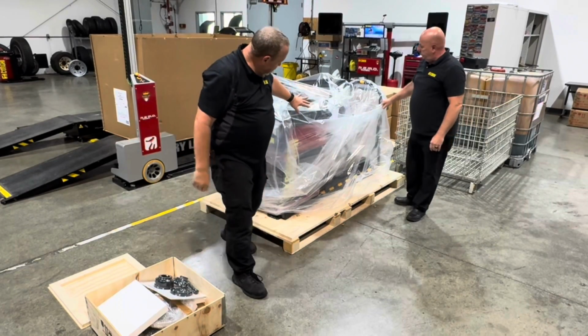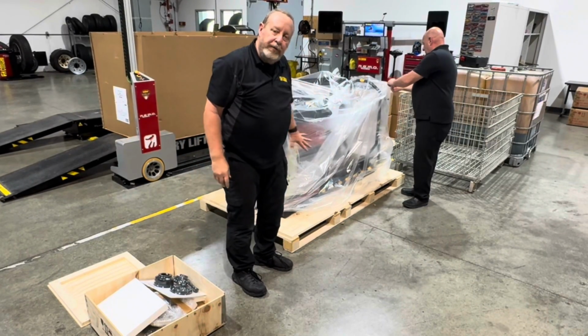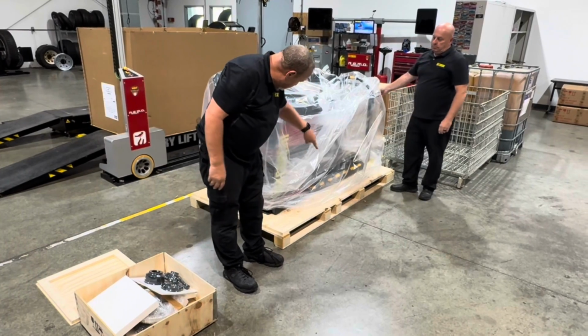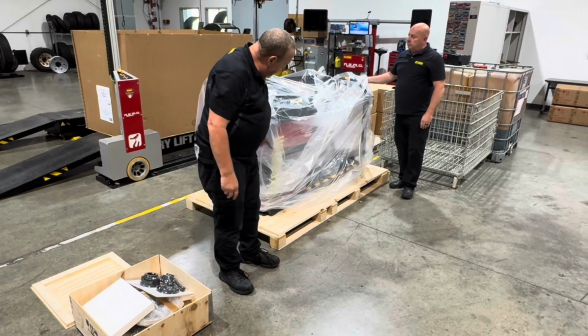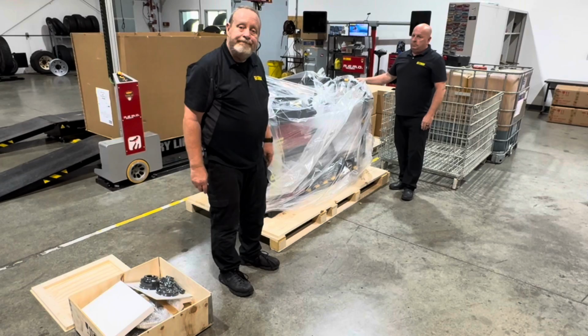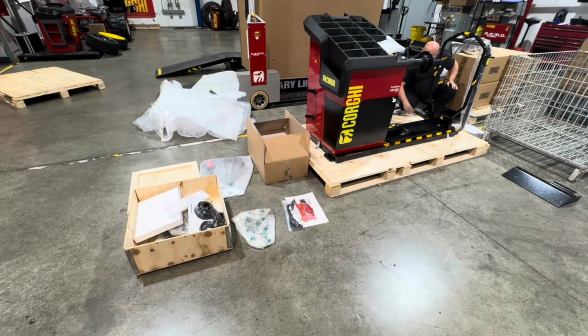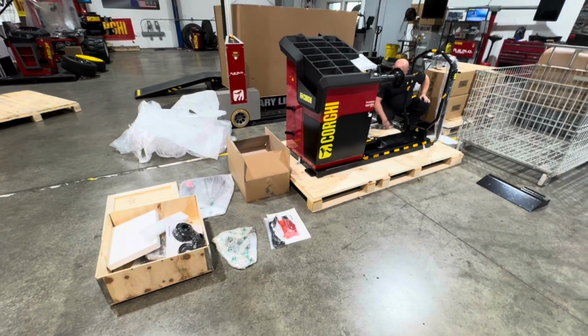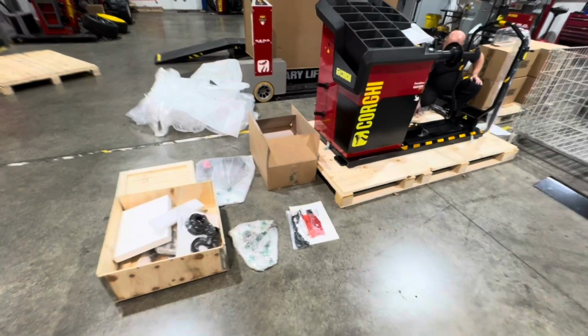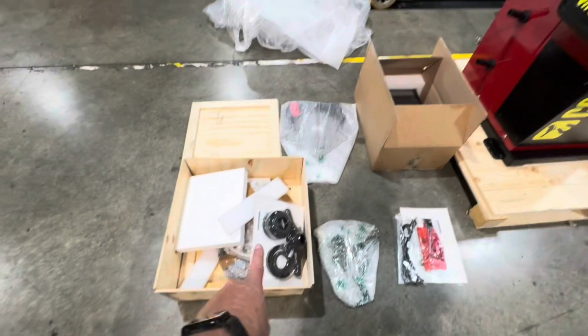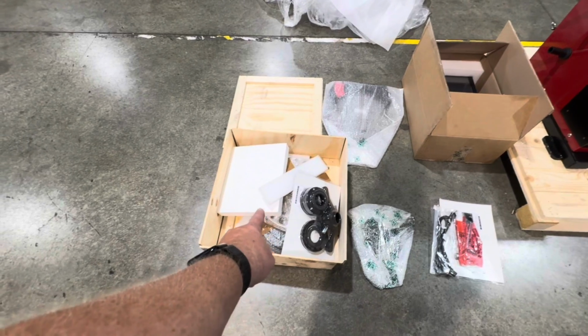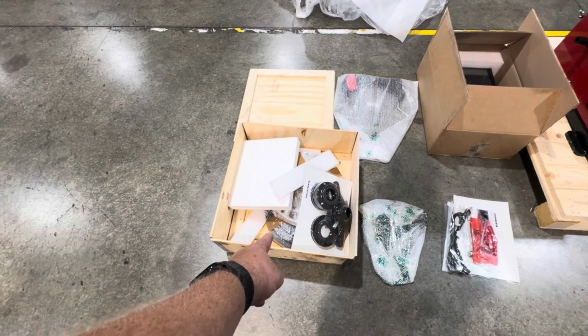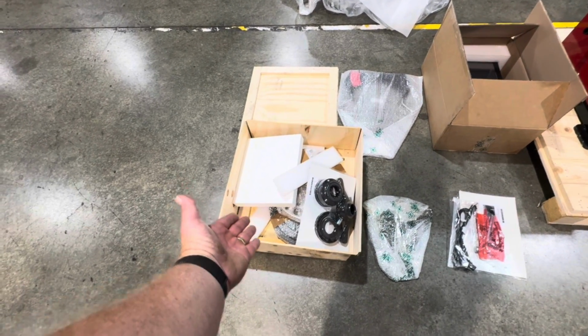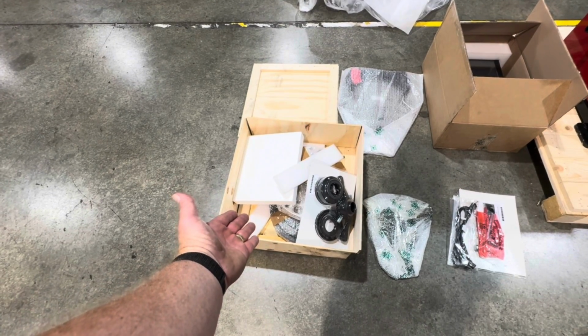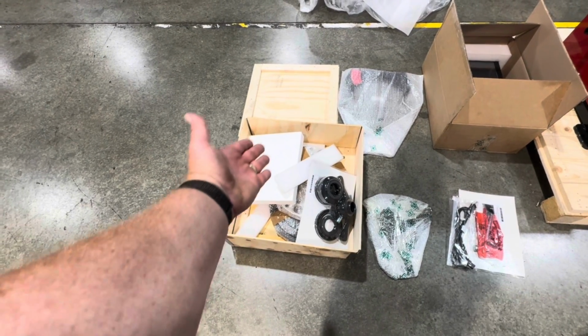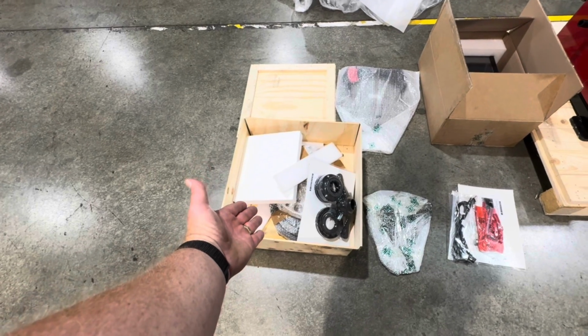Next, remove all packing material, including the mounting bolts around the balancer that mount it to the pallet. We're removing all the packing material from the pallet, and we've opened the crate that has the pin plate and back cone spacer. It's a hub plate with a pin plate that comes standard with the 1680.